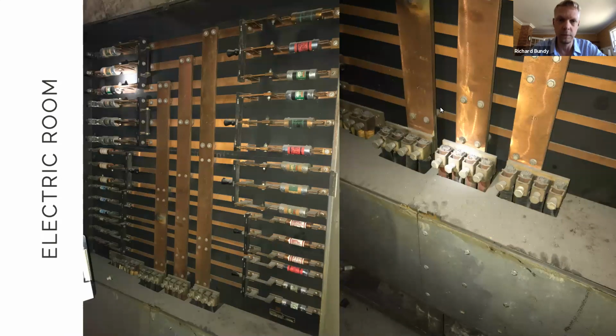So this is the owner's distribution board opened up. As you can see, it's fairly archaic, but everything is in good working condition. It's a 120/208 system. You can see your phases and your neutral coming in at the bottom of this panel. I would assume this would be the tie-in point for the automatic transfer switch. You'd probably have to pull these cables off the lugs, extend them out to the ATS, and then have the ATS output come back to this panel. It's fairly tight working condition, but there is some room available to do the work and to install the additional conduit that you're going to need. So it's going to be a challenge, but we think it's very doable.